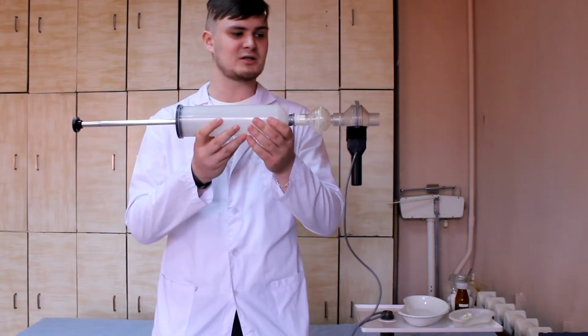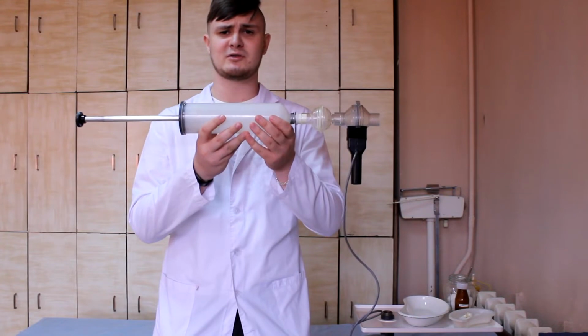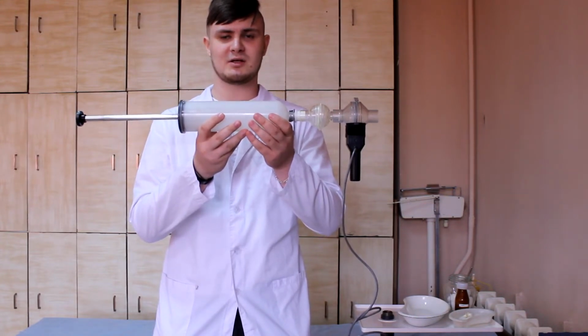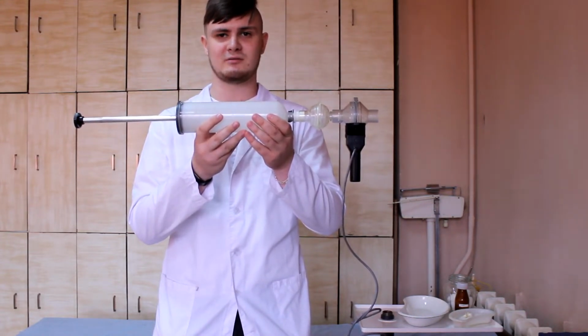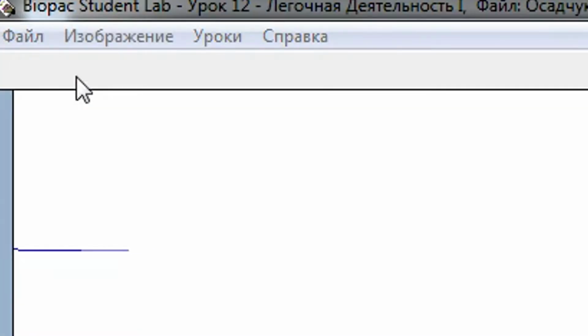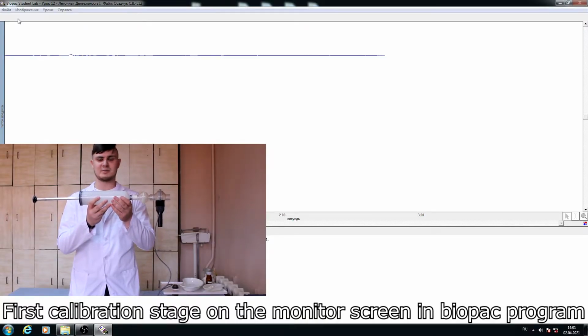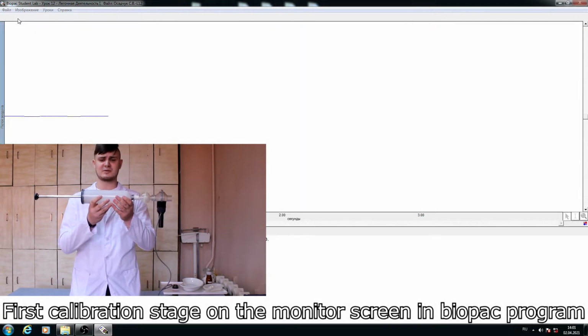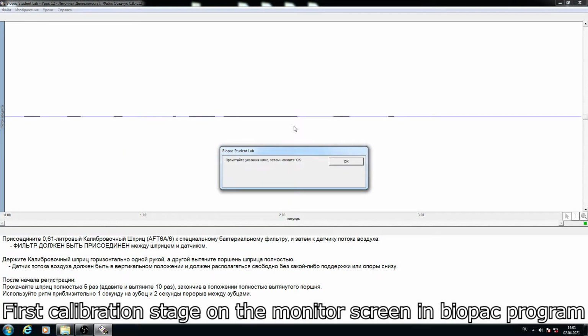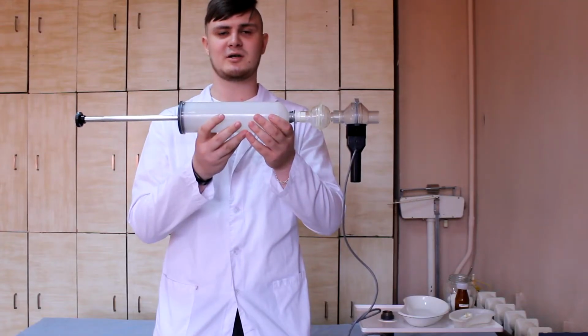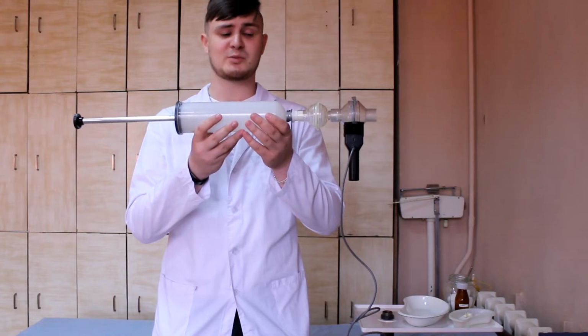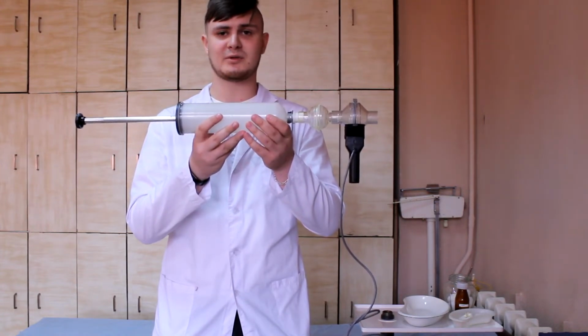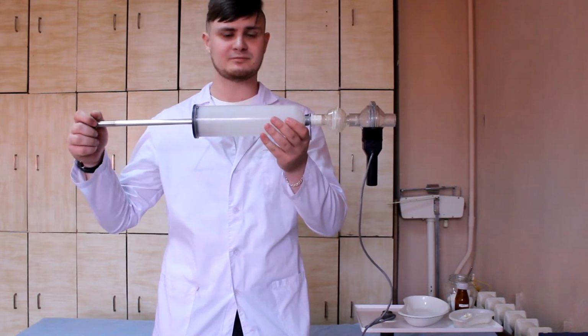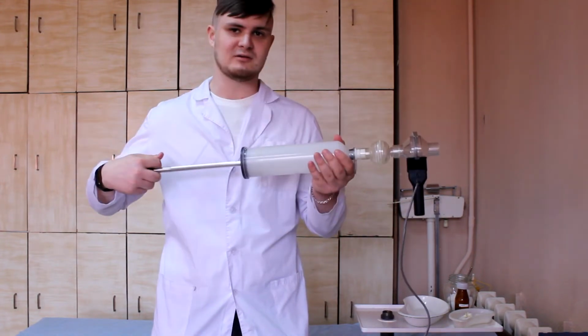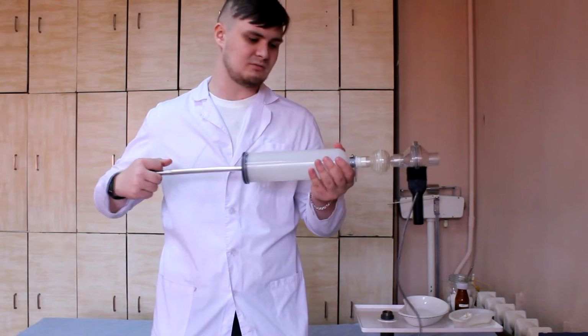Now for 8 seconds we need to hold the airflow transducer in the same position, since it's very sensitive to any fluctuations. During the second stage of the calibration, we need to move the plunger throughout the entire process, until the notification about the end of calibration appears. You will need to push the plunger once every 2 seconds.